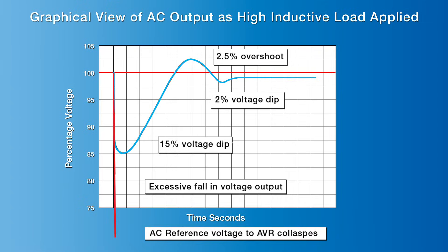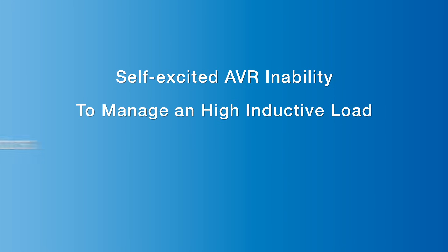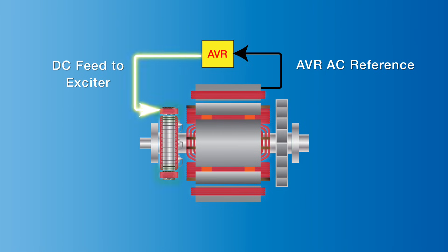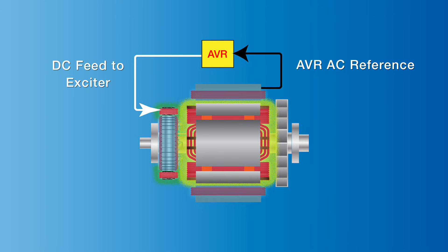When choosing a generator, the system designer takes into account a self-excited generator's inability to manage an inductive load mainly comprising electric motors. As long as the AC reference voltage from the stator to the AVR stays above 60 to 70%, the DC feed to the exciter will continue feeding the main rotor, generating a magnetic field to maintain AC output from the generator to the load.